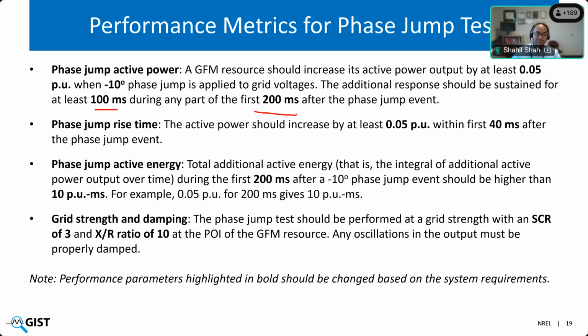after the disturbance. So we don't want to say that it should be higher than this particular level for 100 milliseconds, but it's more like any 100 millisecond within that 200 millisecond to accommodate different shapes of the response. The second part is phase jump rise time, how fast the response should rise. So it should rise to this particular level within the 40 millisecond after disturbance.